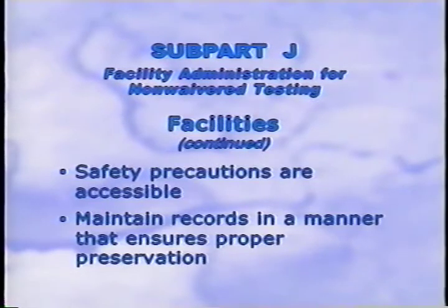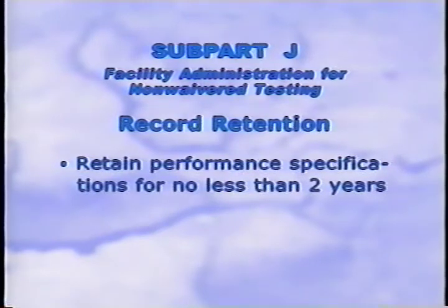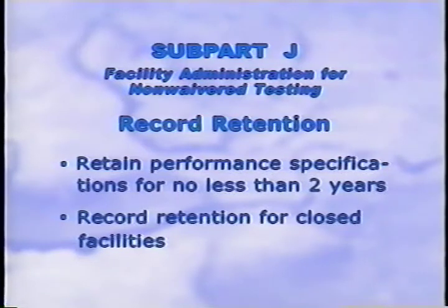One is in the second standard, transfusion services. Facilities that provide transfusion services must now report transfusion reactions to laboratories and federal and state authorities. The last two are in the standard record retention. Records of test systems performance specifications that are established or verified by the laboratory must be kept for the period of time the laboratory uses the test systems, but no less than 2 years. Laboratories that cease operation must retain all records for the specified time frames in the regulations.